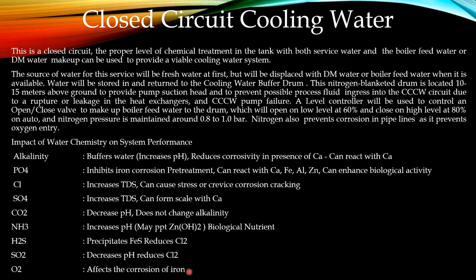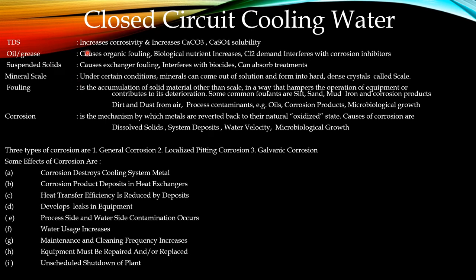Hydrogen sulfide will precipitate ferrous sulfide and reduces chlorine. If sulfate is present, that will decrease the pH and reduce chlorides. Oxygen affects the corrosion of iron — oxygen will oxidize the metal surface, which increases corrosion in the pipeline. Total dissolved solids (TDS), if present, increases corrosivity and increases calcium carbonate and calcium sulfate solubility in the cooling water. Oil and grease cause organic fouling, act as biological nutrients, increase chlorine demand, and interfere with corrosion inhibitors. Suspended solids cause exchanger fouling and interfere with biocides and can absorb treatment chemicals.